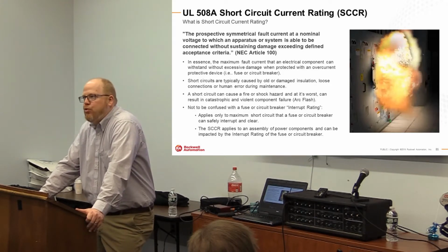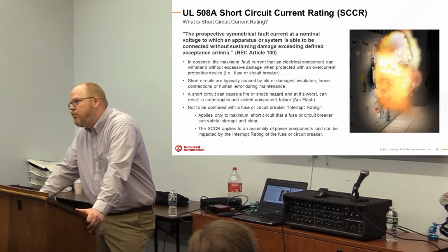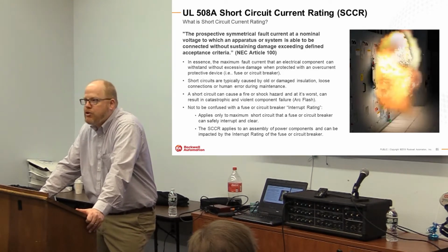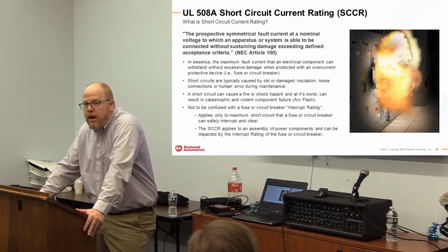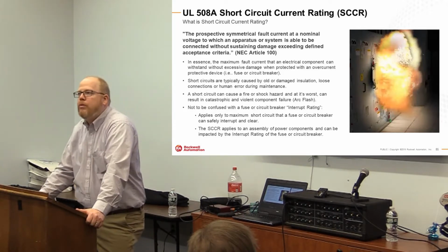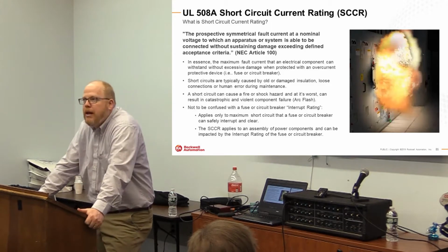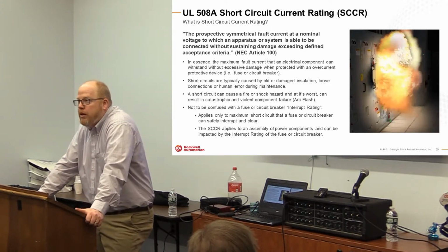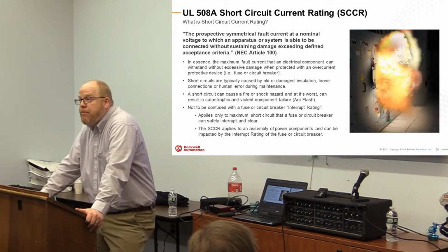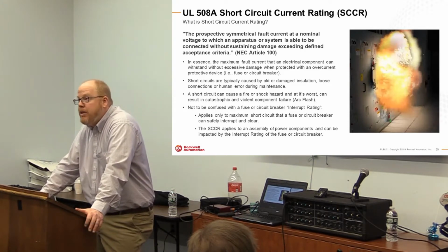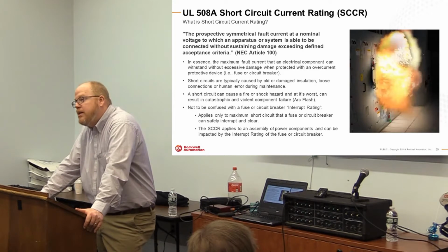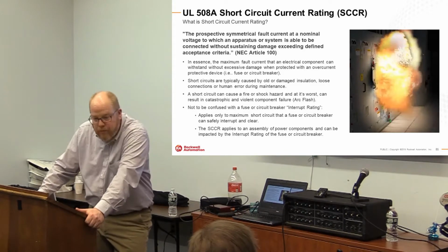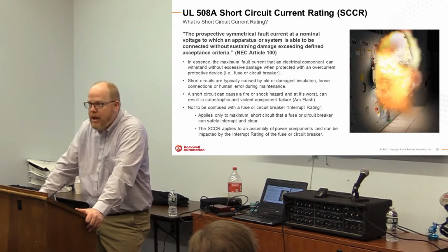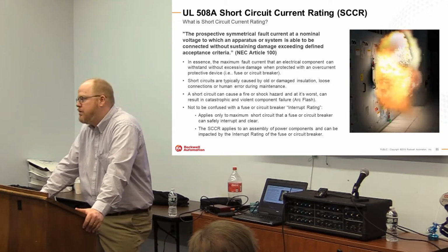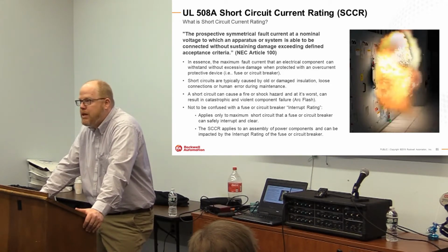But let me share with you the reason why we talk about SCCR, and that's what that really cool explosion picture is. Well, it's cool unless you're the guy standing in front of it. But what is short circuit current rating? I'm just going to quote the NEC, Article 100. It's the prospective symmetrical fault current at a nominal voltage to which an apparatus or system is able to be connected without sustaining damage exceeding the defined acceptance criteria. In a nutshell, this is what can be connected to a system when it blows up and doesn't hurt anybody. Fire and shock protection.